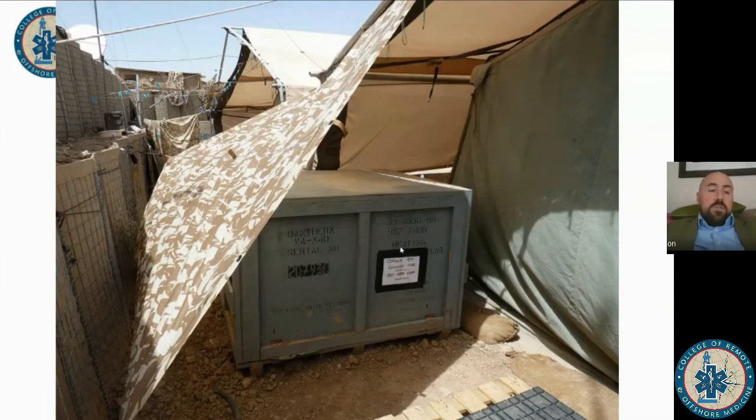Gas, if you've got oxygen or Entonox or anything like that, where are you going to store it? You're going to store it somewhere safe. Is it going to be somewhere that is out of direct sunlight? Is it going to be kept chilled? Or, where are you going to put it? This is just an example of a storage facility for oxygen cylinders. And guess what? It gets pretty hot there. So according to the manufacturer's specifications, it's not ideal to store anything above 25 degrees, but sometimes it's impossible.